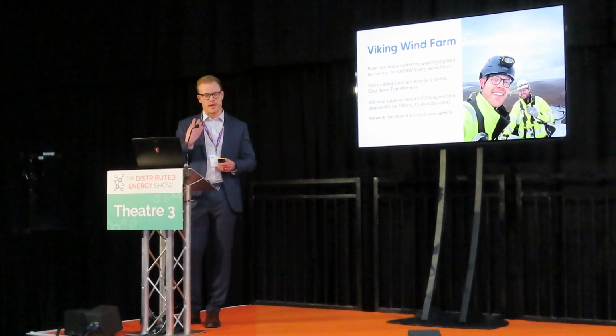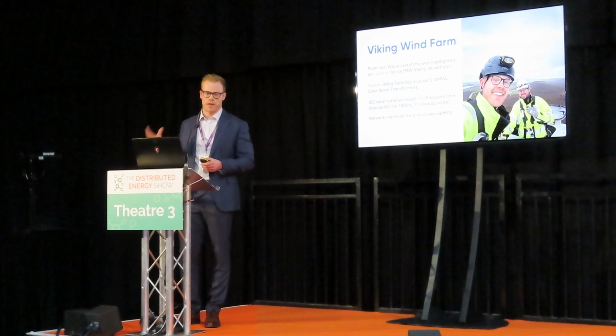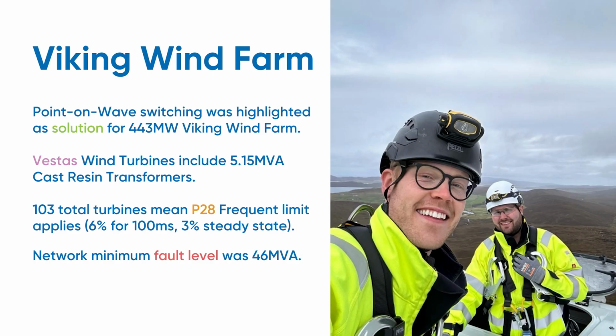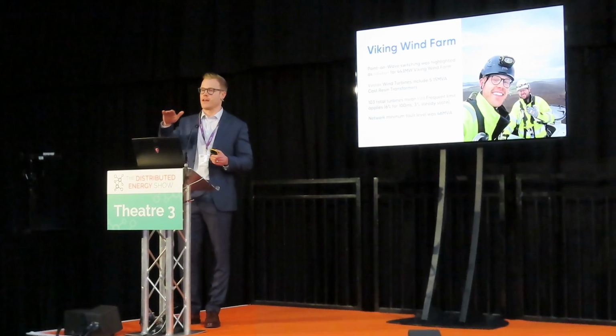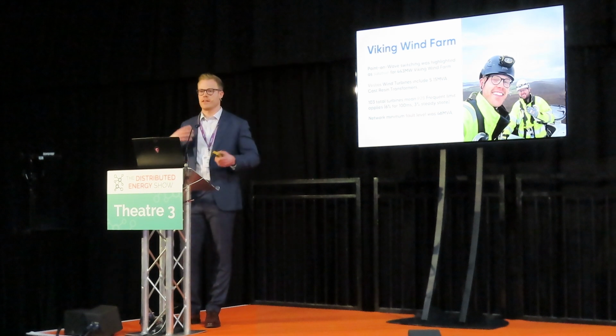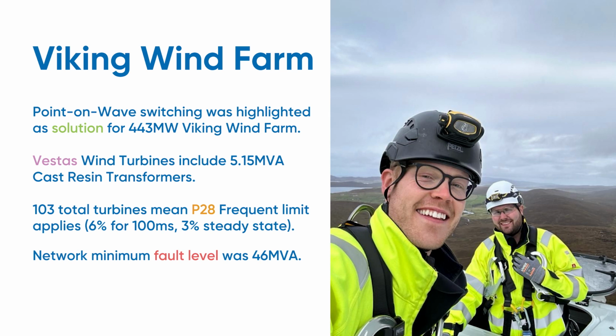Now, the issue is that if you think about a 443 megawatt wind farm on the Shetland Islands, the Shetland Islands' current network is not very big, it's not very strong. Now, there's an HVDC interconnect being built specifically for this wind farm. So that's going to take the electricity generated on the Shetland Islands and send it to mainland UK. Now, the problem is you can't assume that the HVDC interconnect is going to be on, working 100% of the time. If you lose that HVDC interconnect, you cannot leave 103 turbines with no power on the Shetland Islands because there's wind, there's rain driving in, and turbines need to rotate their nacelle to point into the wind at all times. And they also need to keep their motors warm, the oil and the lubrication running. So they need power at all times.